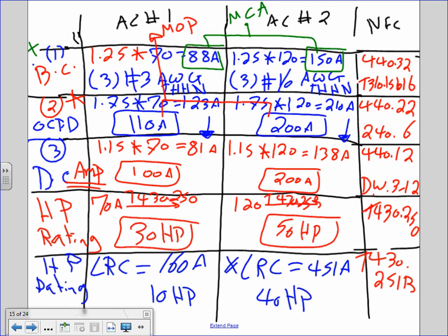Now you have two horsepower values for each motor: chiller one has 10 HP from locked rotor current and 30 HP from full load current; chiller two has 40 HP from locked rotor and 50 HP from full load. You pick the largest. So chiller one uses 30 HP and chiller two uses 50 HP for the disconnect rating.